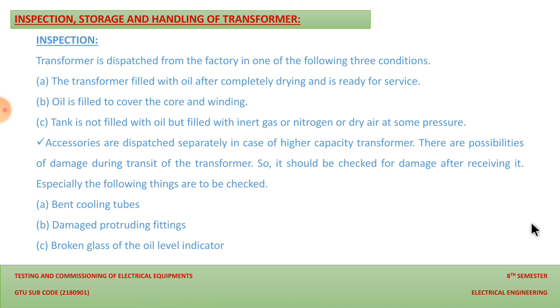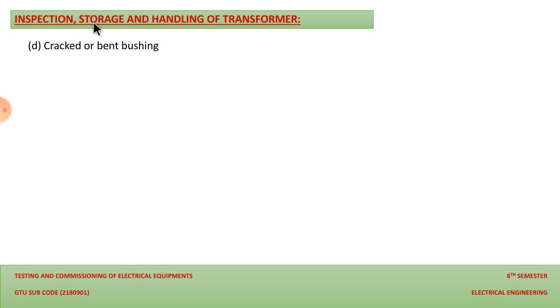And the next point that you have to inspect, in the case of inspection, storage and handling of the transformer, is cracked or bent bushings. Bushings are provided on the top part of the transformer casing, and generally we take out the live terminals from the transformer through them. Bushings provide the insulation between the transformer tank and the conductors that we are taking out from the transformer. So if the bushings are cracked or bent, then we have to replace them by calling the vendor, and it is damage which happened during the transit.